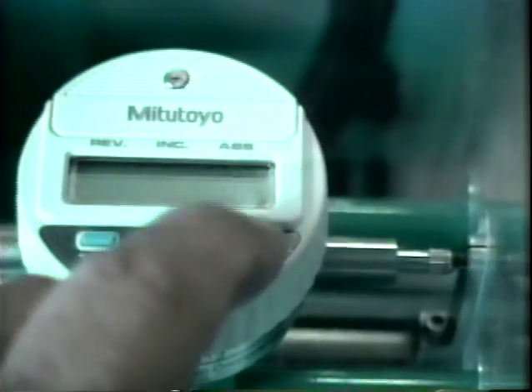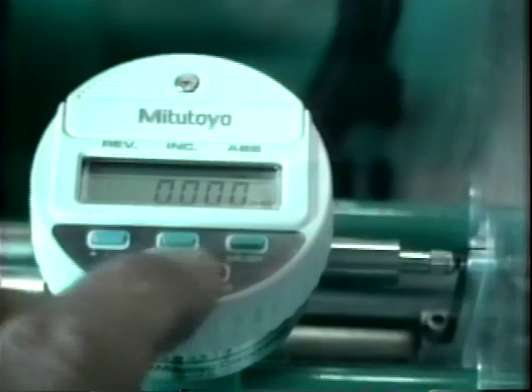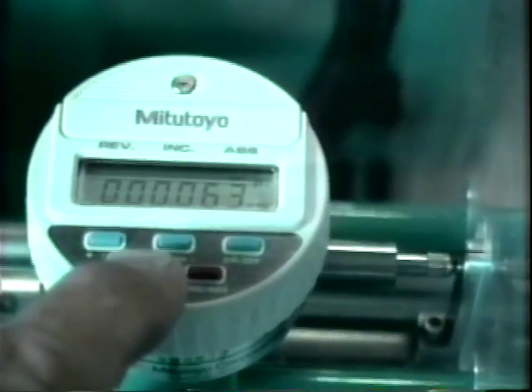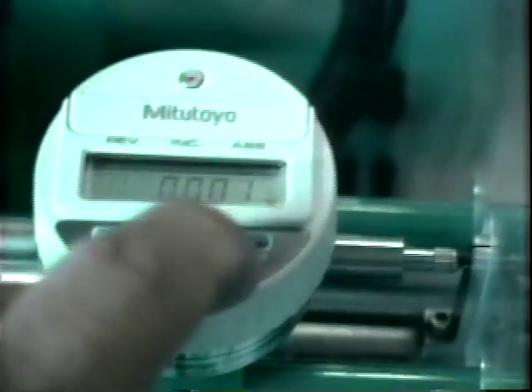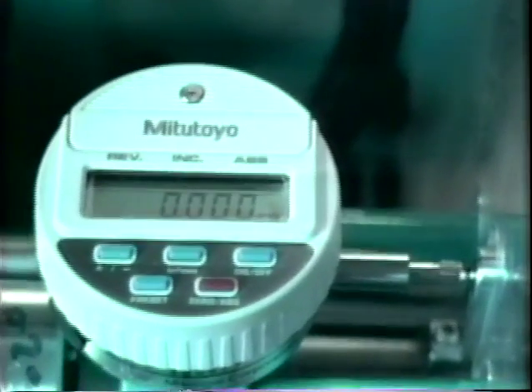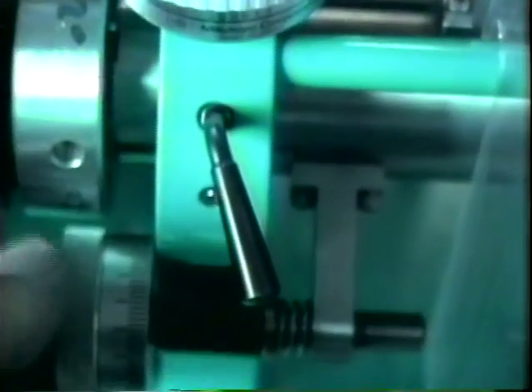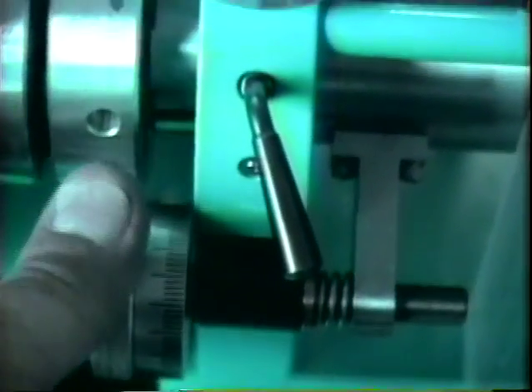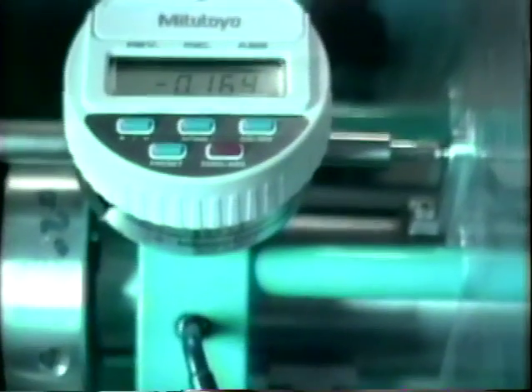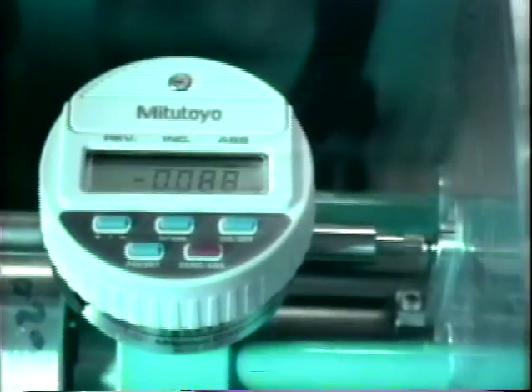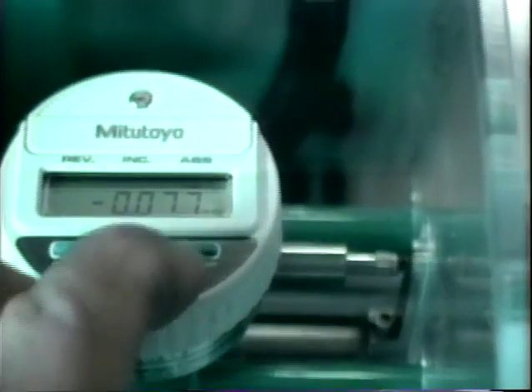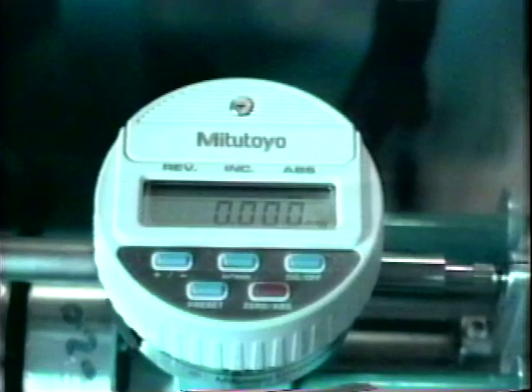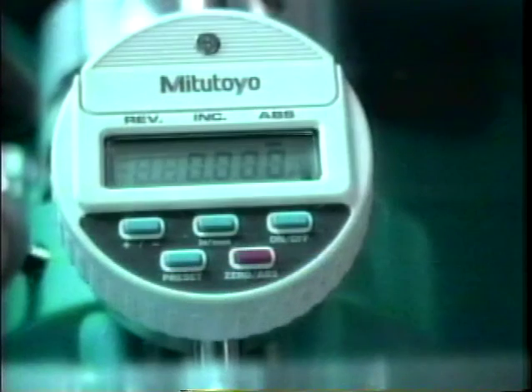For those of you that have the very latest Microtrim Phase 3 machine, you'll have the digital indicator. This digital indicator is coupled with the micrometer dial in the same way as the dial indicator, but the digital indicator is much more accurate. And to reference this indicator to 0, you only have to hit a button like that. The most important feature of this digital indicator is longer travel on the rod. Instead of 20 thousandths of an inch, you have 500 thousandths of an inch.